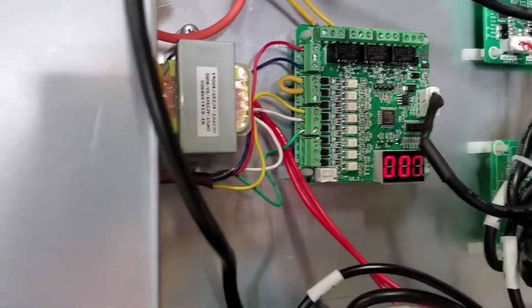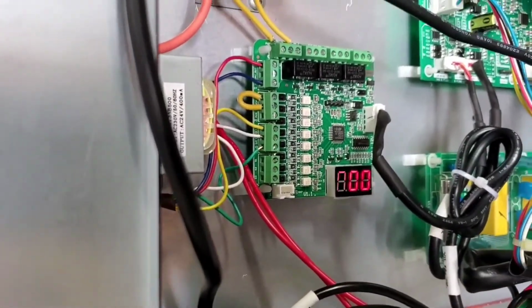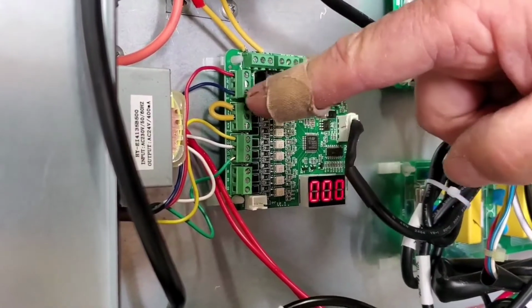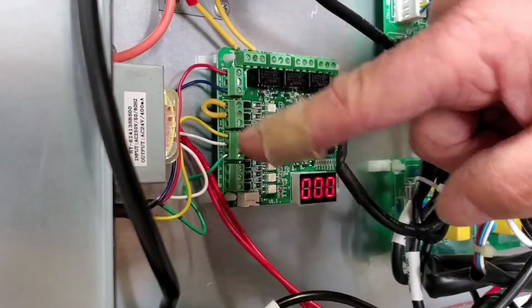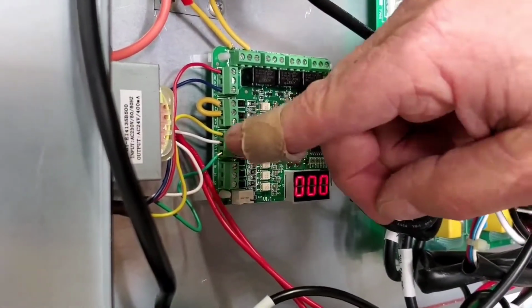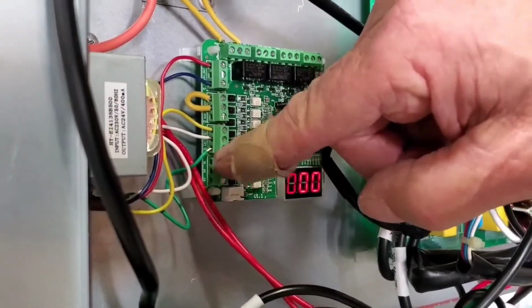Now if you look here real closely, you see red and blue at the top. That's your 24-volt out, your common. Then you have the yellow jumper, that'll already be there. Then you've got the yellow for compressor, white for heat, green for fan.